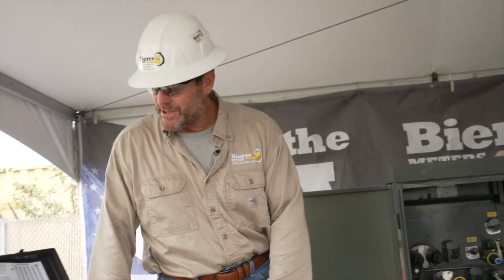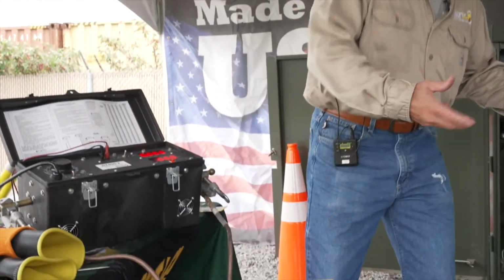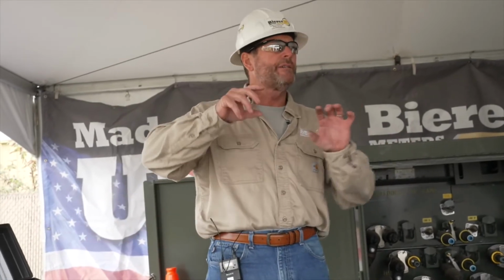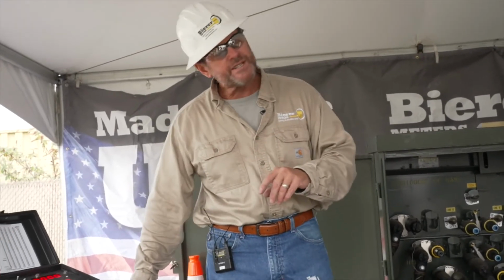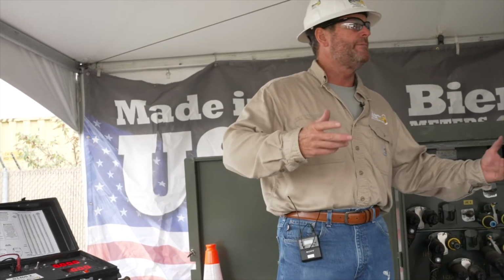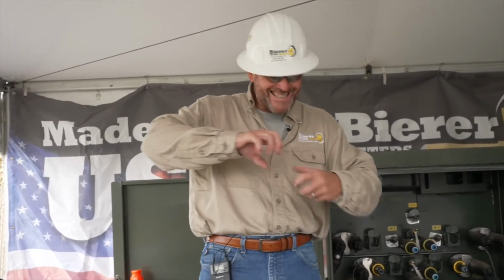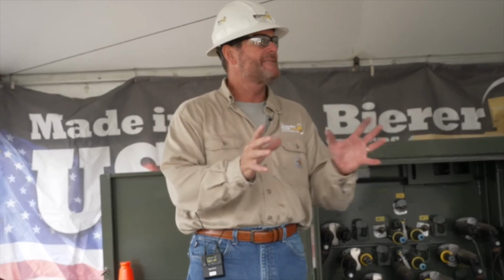Visual inspection, and you also want to do a mechanical inspection. Grab hold of that assembly and verify that the cable is nice and tight in the crimps on your ferrule. You shouldn't be able to wiggle it or pull it out. There's no movement, solid like a rock.